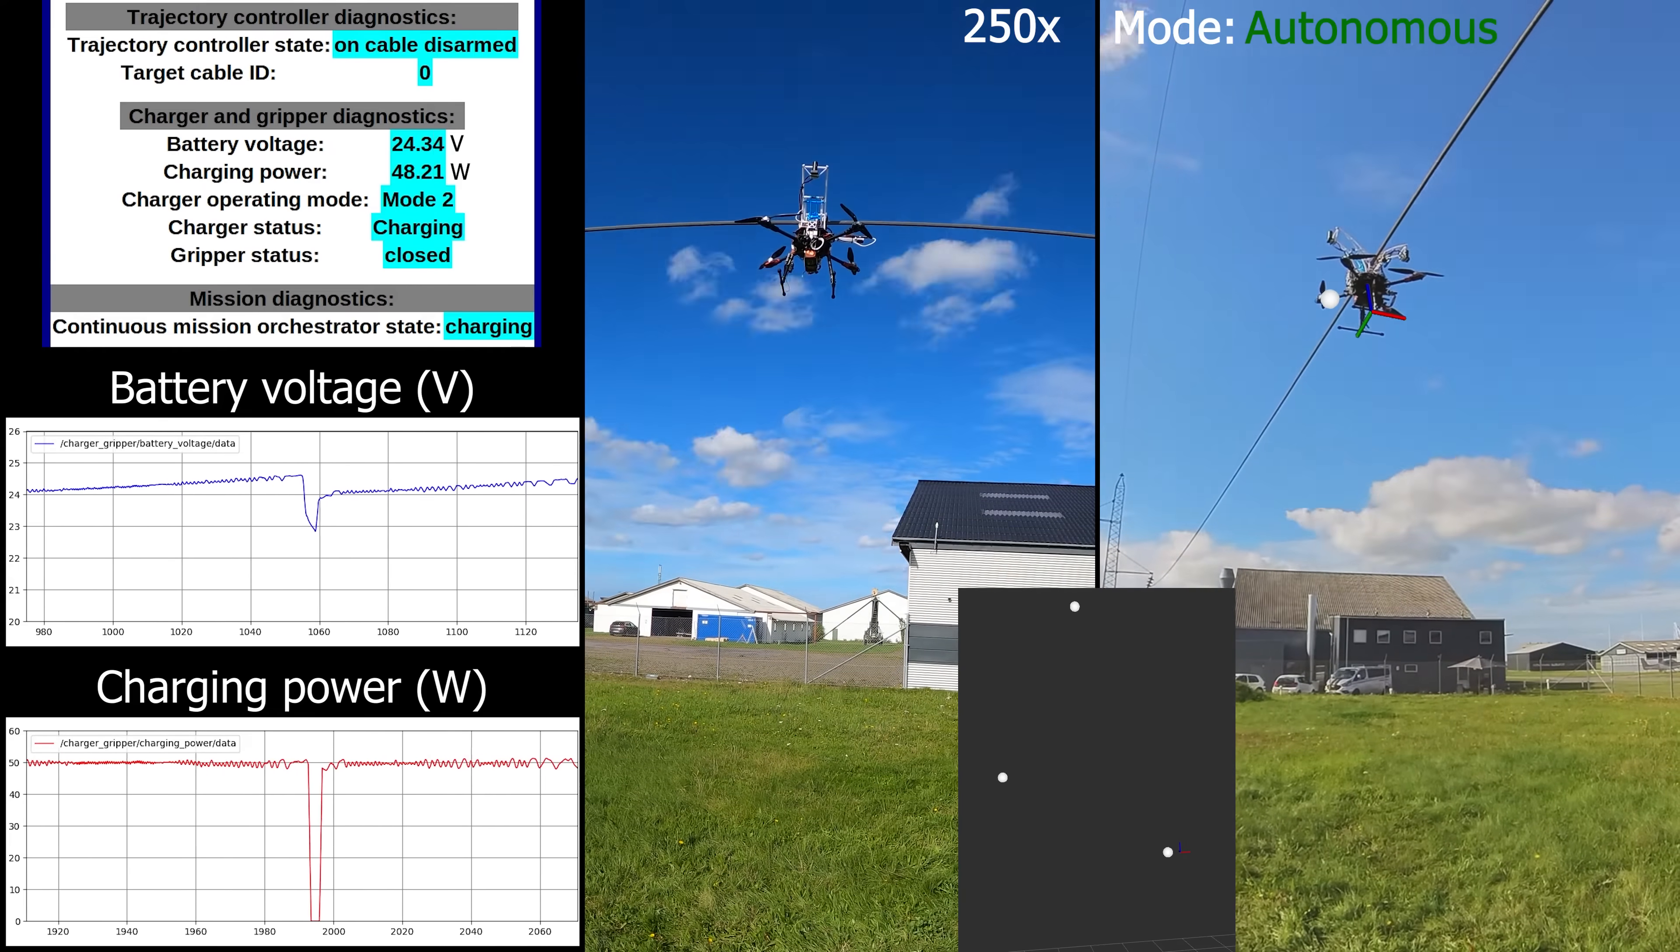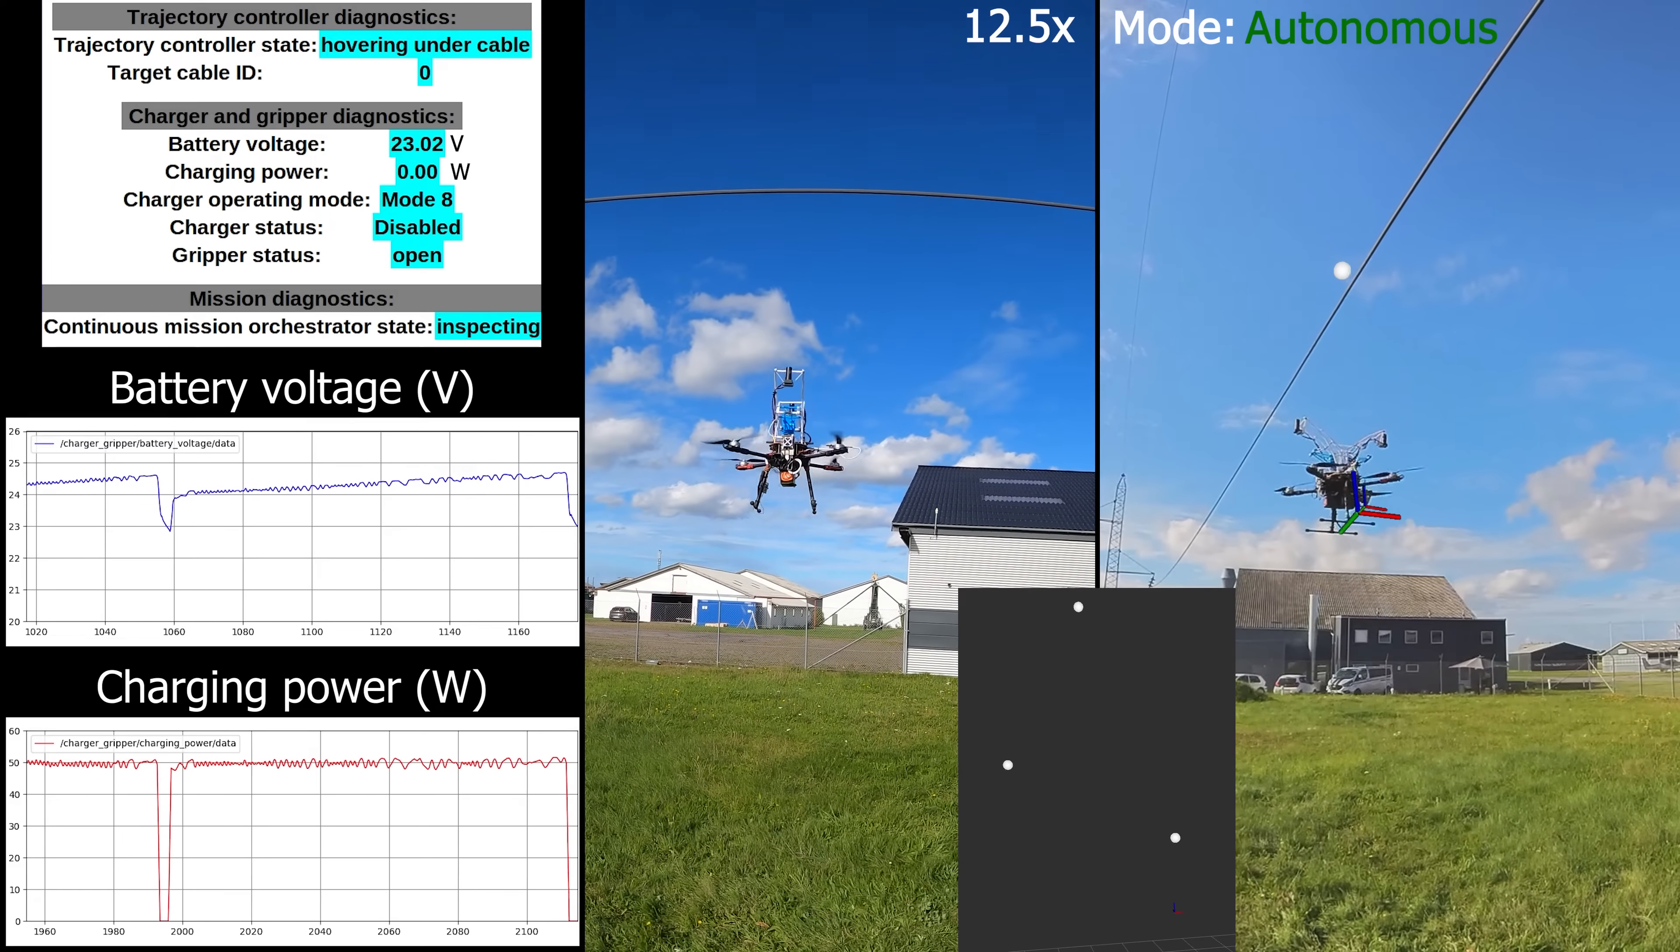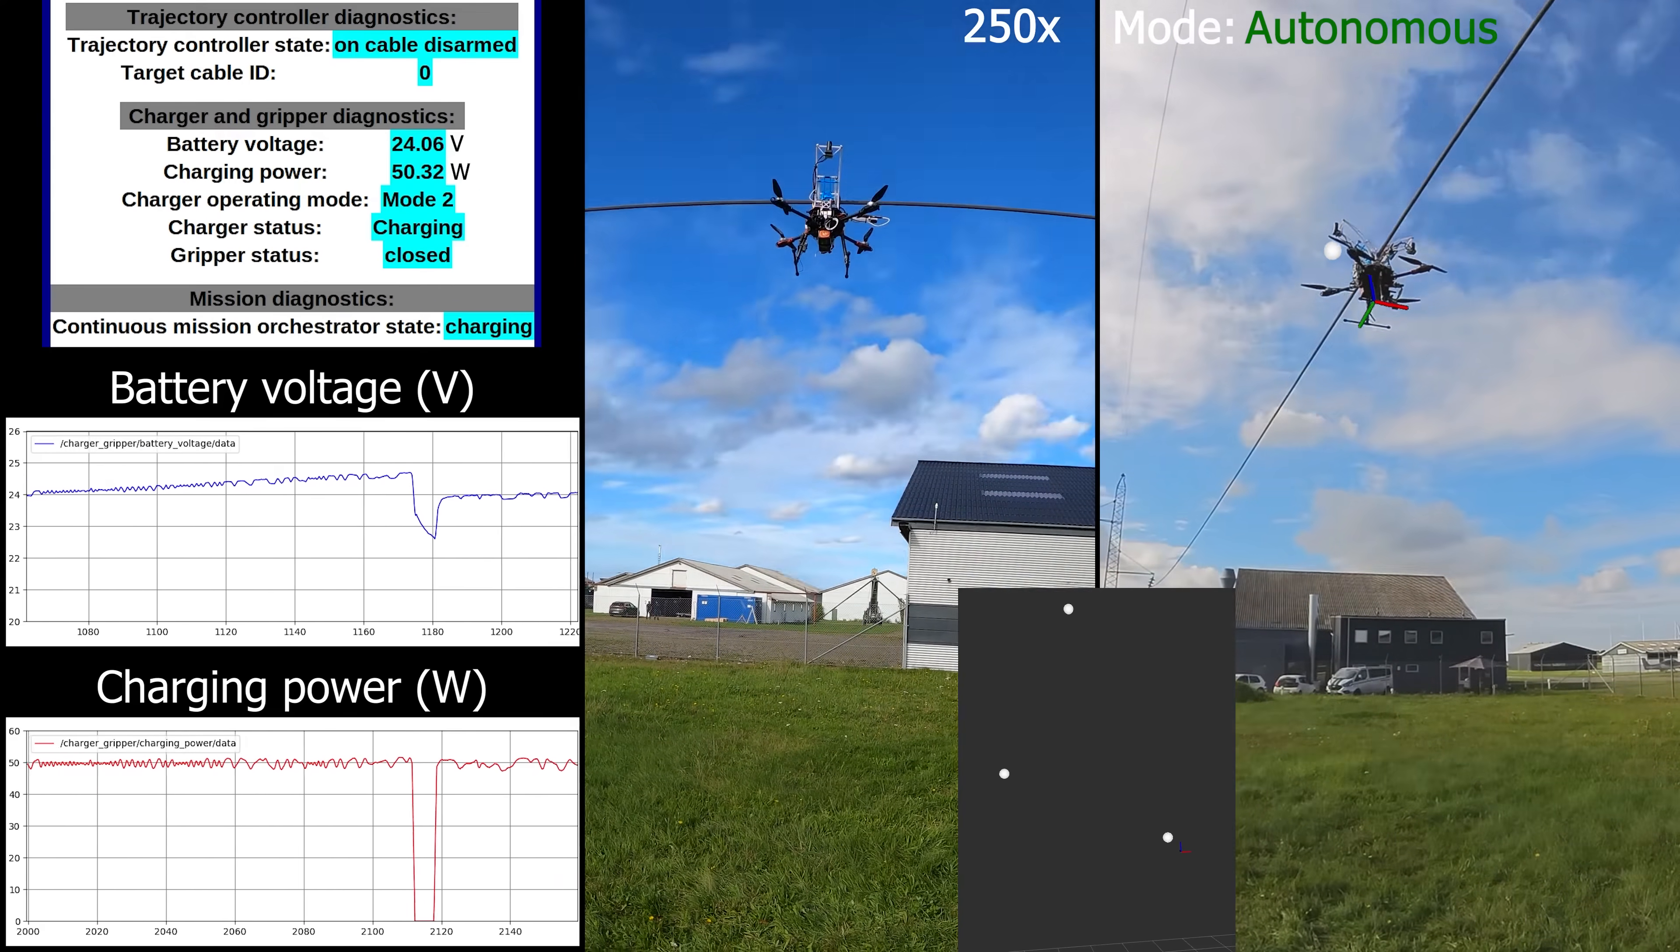The current in the power line was approximately 300 amperes from which the energy harvesting device was able to charge the battery with 50 watts. A higher power line current would result in a proportionally higher charging power.